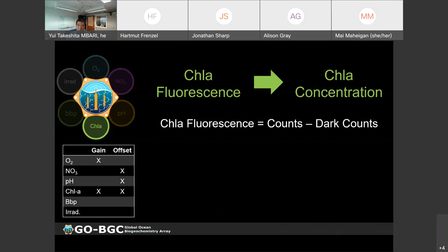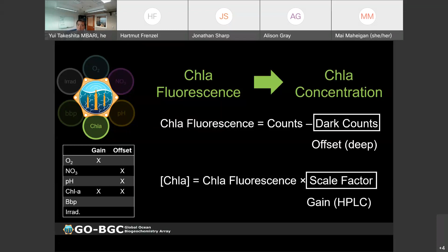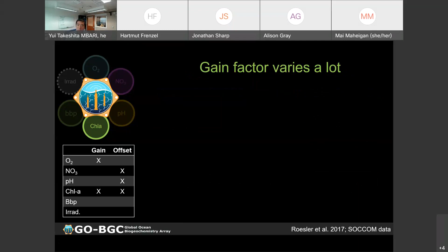And then in order to go from this fluorescence to a concentration, we have to multiply by a scale factor. And this is where the gain correction comes in. Currently we apply a scale factor of 2, and this is based on comparisons of fluorometers and HPLC samples taken around the world. We chose 2 based on results from Roesler et al. in 2017, where they demonstrated that the global average of this correction factor is about 2.